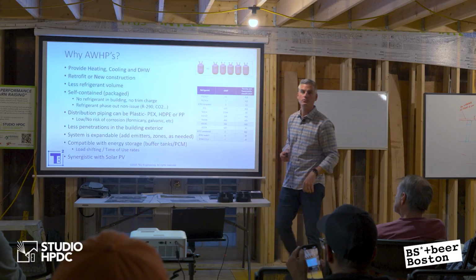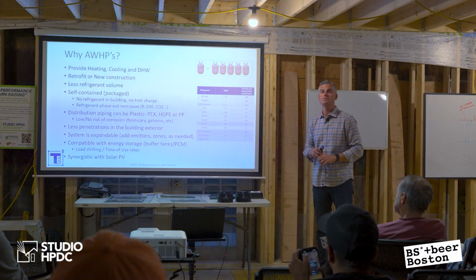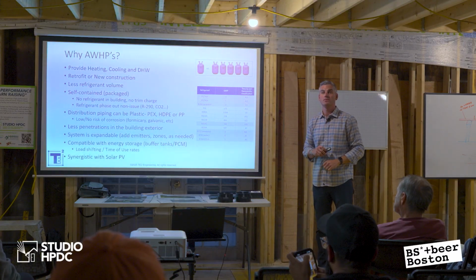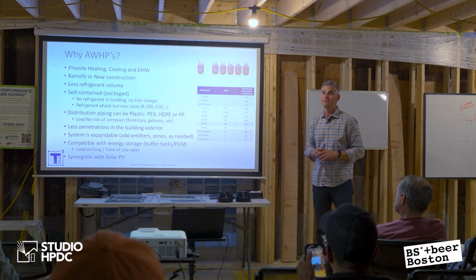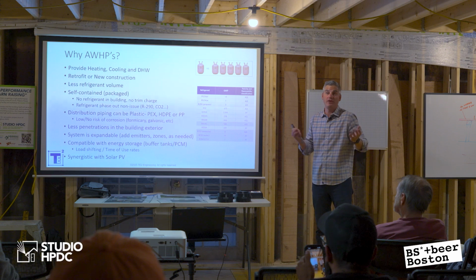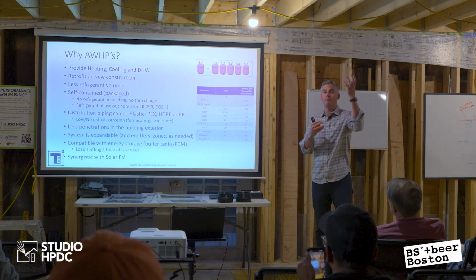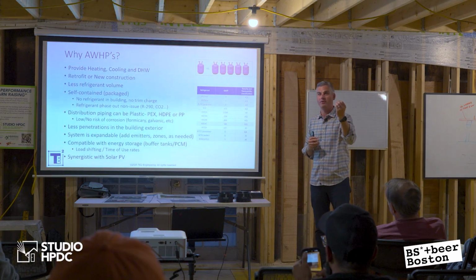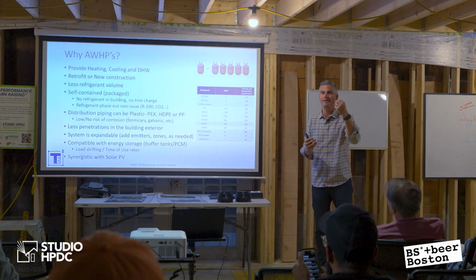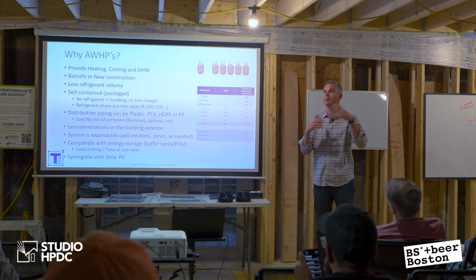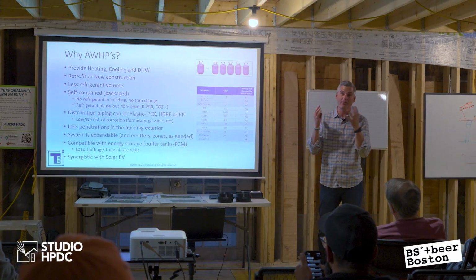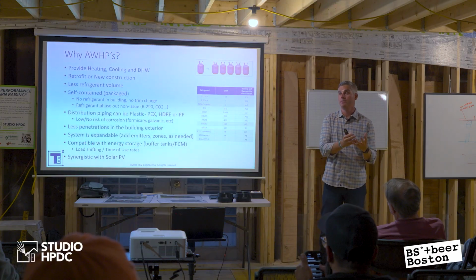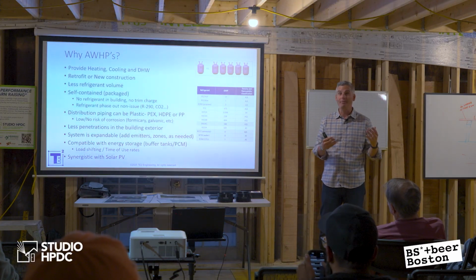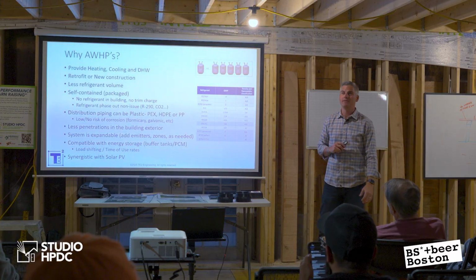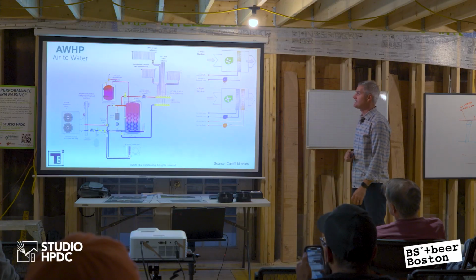You mentioned the refrigerant phase-out being a non-issue for this system in particular. I mean, they're still making replacement parts for 410A. Yep, they're only obligated to for 7 years. So after 7 years, you could have a small component fail in an R410A system. It could be a control board, an EEV, an expansion valve, a blower, and you might not be able to get that part for that system. And if that happens, what do you do? So that's a problem.